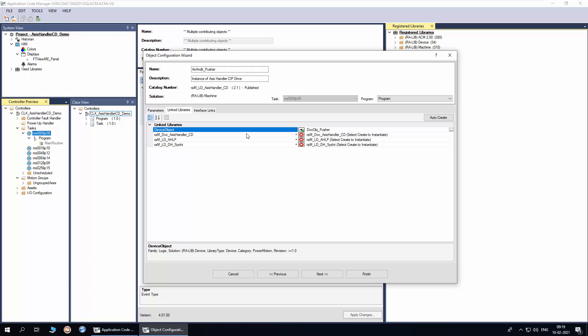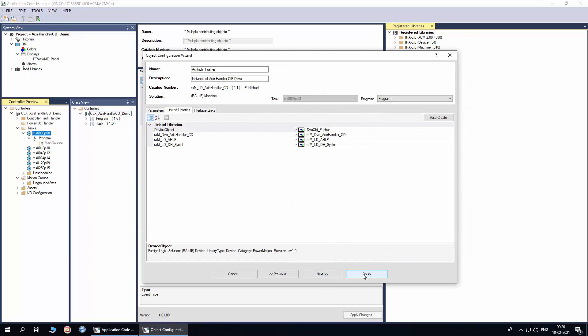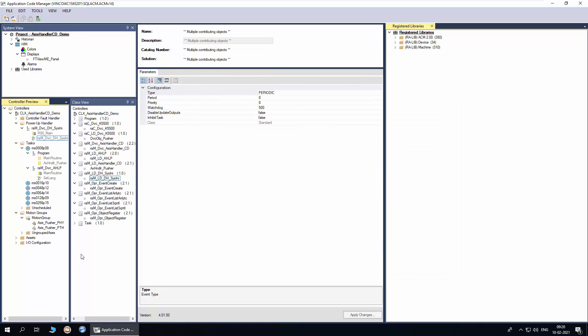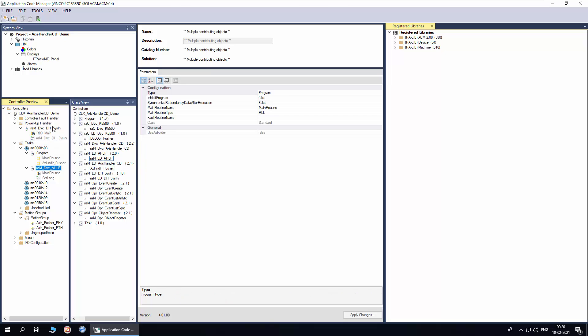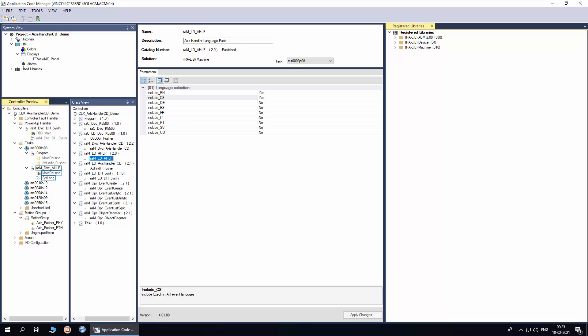Now the device object is added. I will use auto create to create the rest of the linked libraries. Click finish to complete the instantiation. You can notice the axis handler is now added in the program, along with the language pack and system initialization program. The path and physical axis are also added. To select a language other than English, click on the axis handler language pack implement, select the required language, and click apply. To understand further about generating the code and display, watch the ACM workflow basics video series.